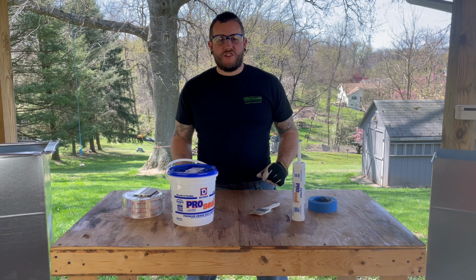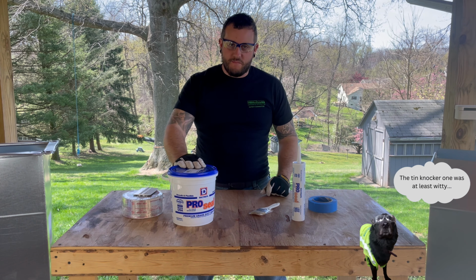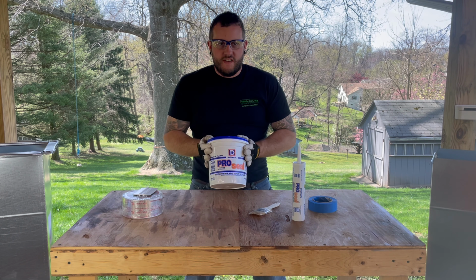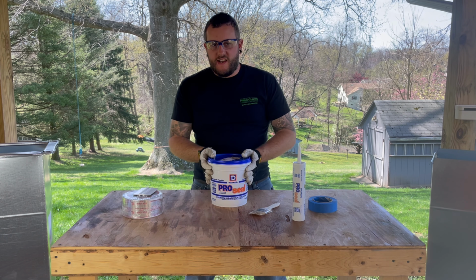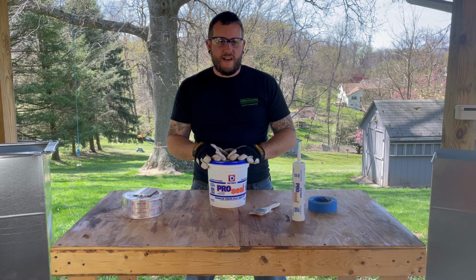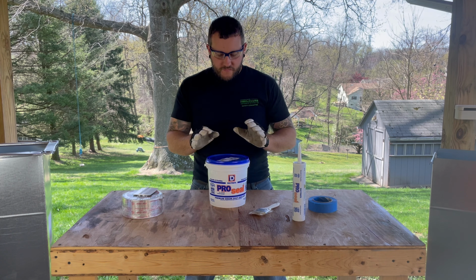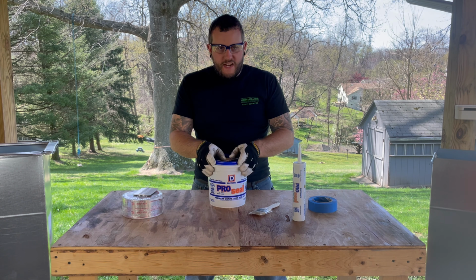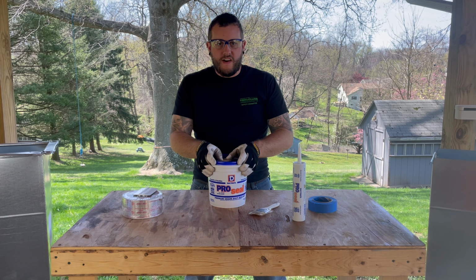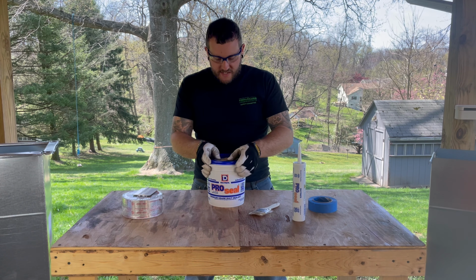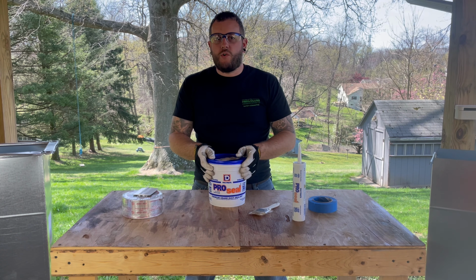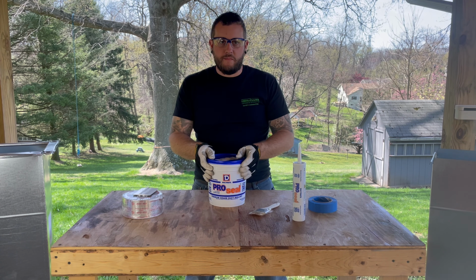All right, now that I've got my shirt on that I'm not worried about getting some duct seal on, a couple things we want to go over. You want to use this stuff right out of the bucket. We don't want to thin it or cut it with water, any of that stuff. It's ready to go right out of the bucket or the caulk tube. We need to make sure that it is stored between 35 and 110 degrees. It needs to be stored between those temperatures, and it can only be applied in between those temperatures.